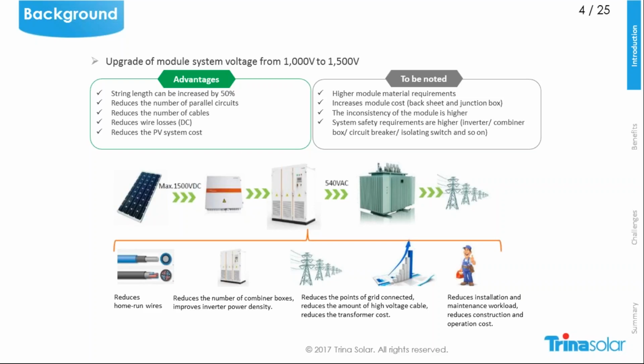Some of the benefits already mentioned here are, for example, the increase of the string length and the decrease of, for example, combiner boxes, circuits and parallel connections, and the increased output voltage of the inverter to have a higher input voltage to the transformer. What is a clear benefit is that it makes a difference if you want to step up from 400 volts or 600 volts to, let's say, 6,000 or 20,000. Later I will also show you some impacts based on this, and we will also speak about the costs and the differences between the systems.